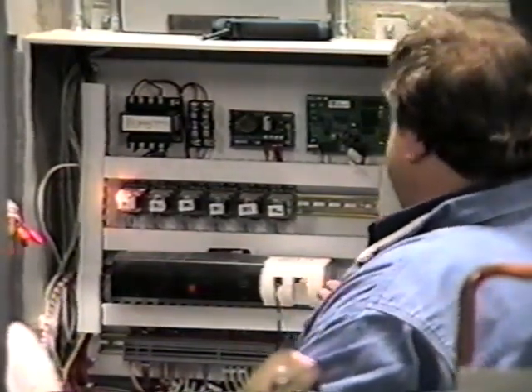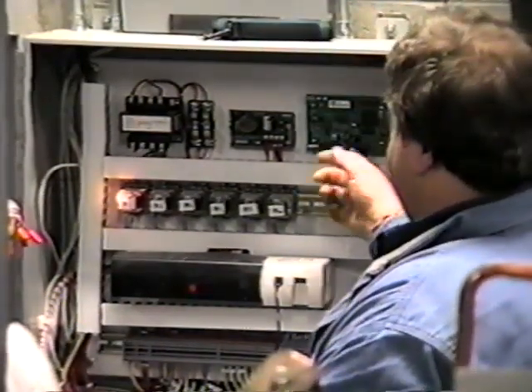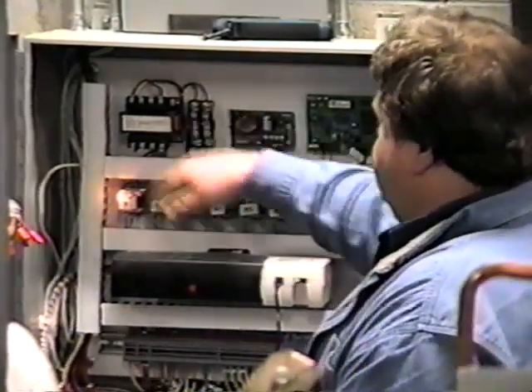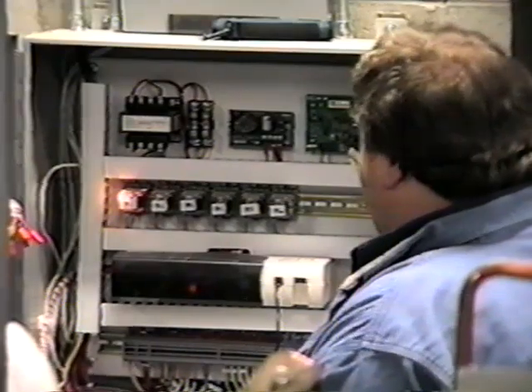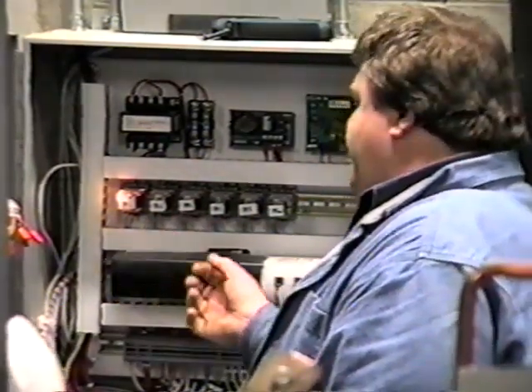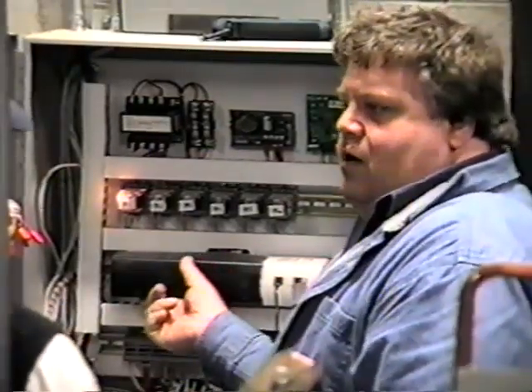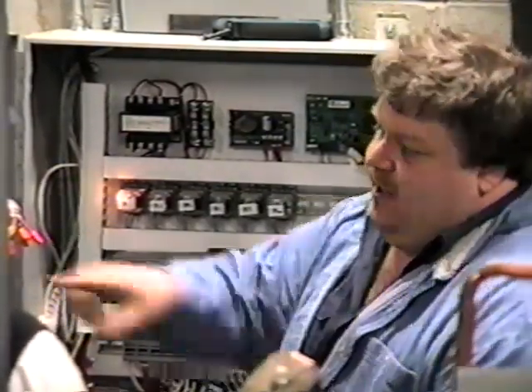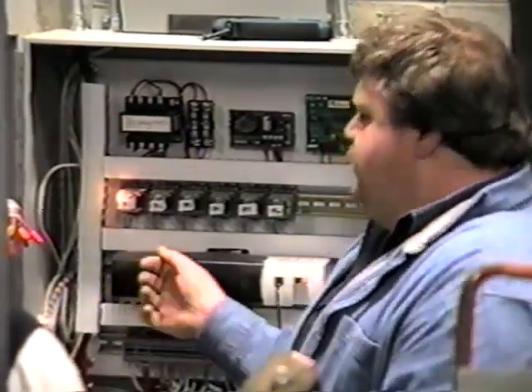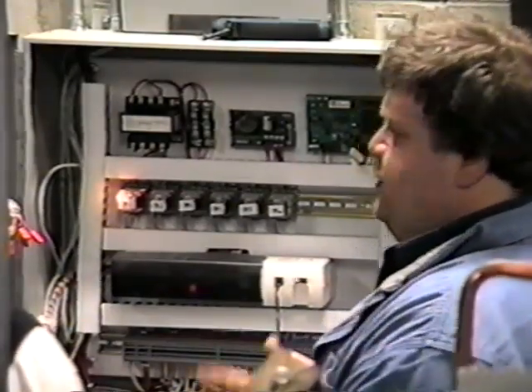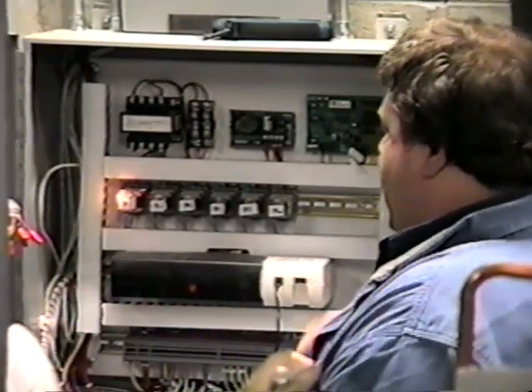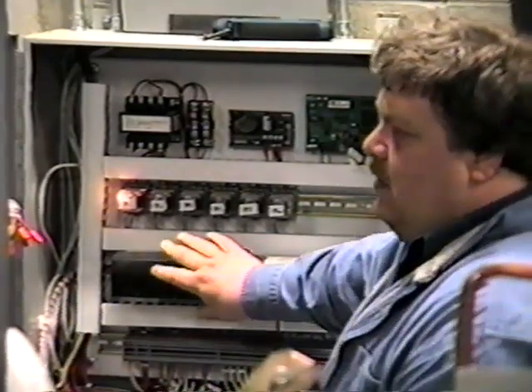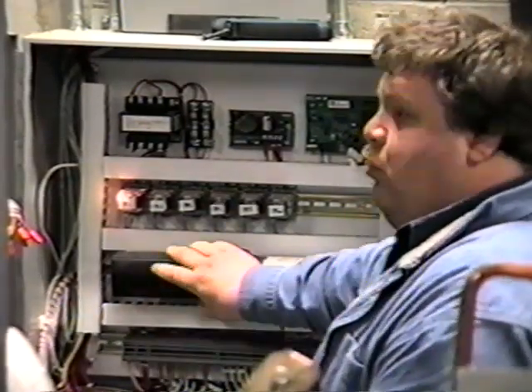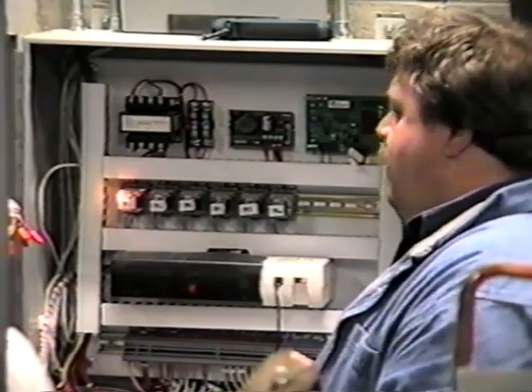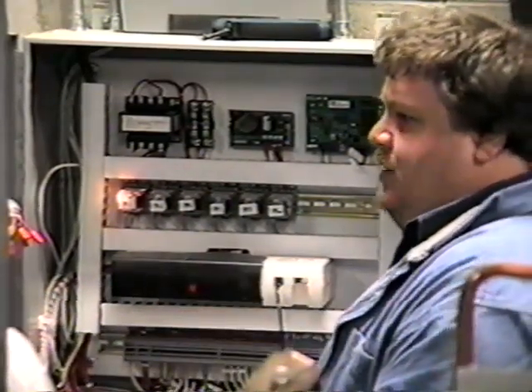So, not much to this thing. It's fairly simple. We've got an infrared sensing board here for your camera, and then just a couple of power supplies. The controller is really good. It does the whole works. It does thermostatic functions, it can do pressure control, all kinds of stuff. That's actually what's in this one: to do the pressure control, it takes the temperatures in that and ramps this fan drive up. So this thing can do tons of stuff, and we're using it for a small portion. As the facility grows, this can also be hooked into expansion modules, and this one brain can run more devices. I think it's up to 7 more expansion modules.